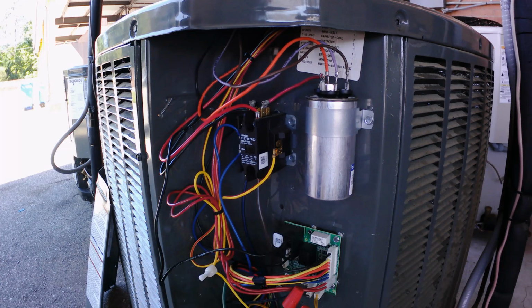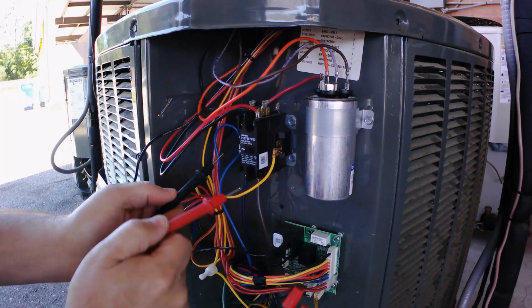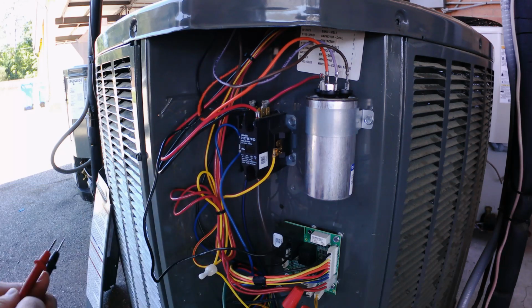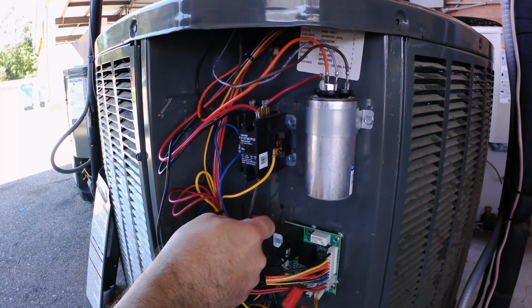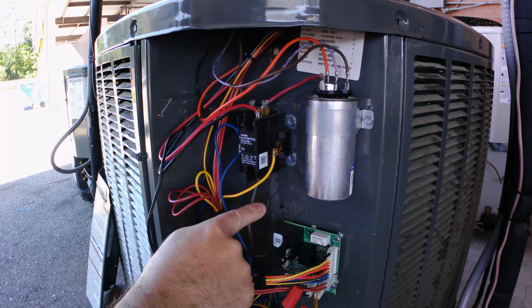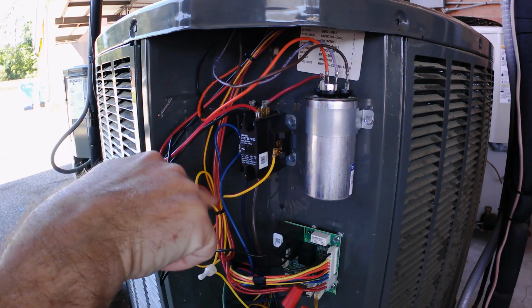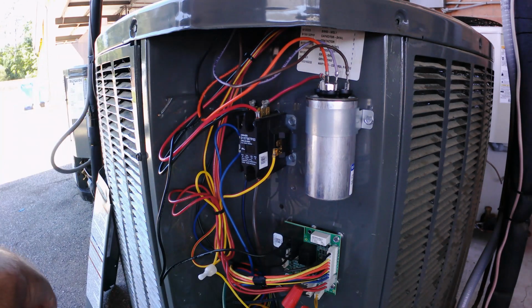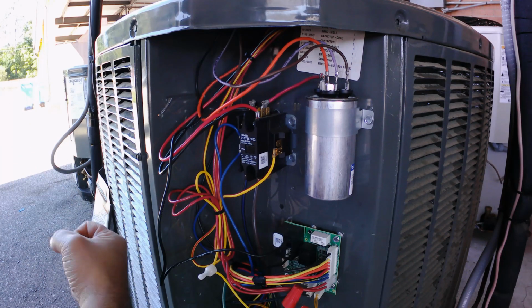You can have the voltage, but if there's not a load, if there's not a coil there to use that power, then it's not going to move that switch. So if you do have 24 volts there and you have a good coil and the switch isn't moving, then maybe there's something internal broken. You're probably not going to see that, but that's when we could do some voltage checks, or if you wanted to, you could remove the power off the bottom and do continuity through it. You can treat it very much the same as a relay.